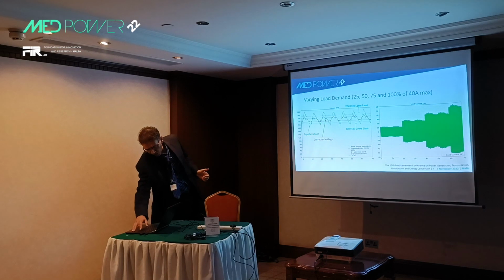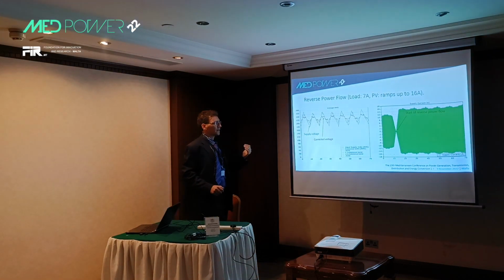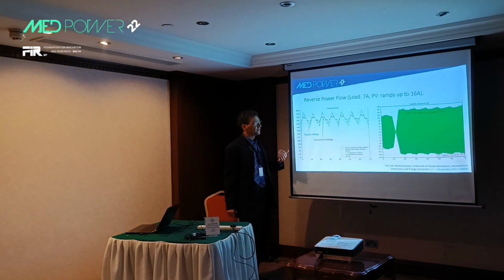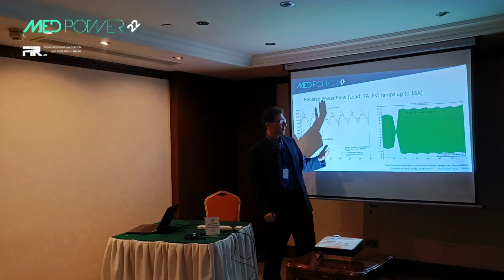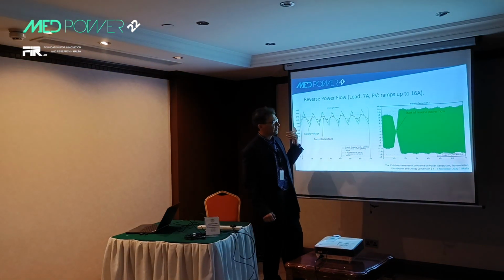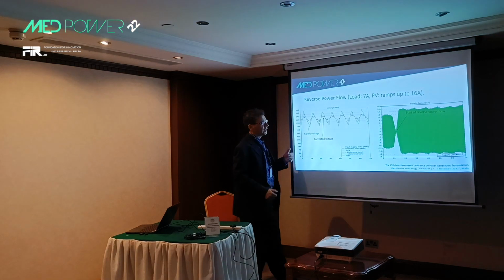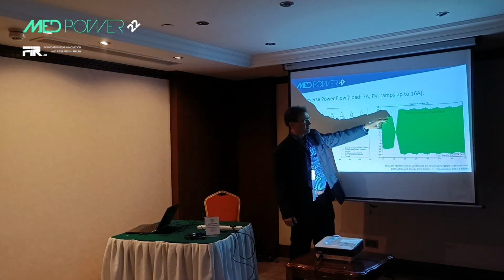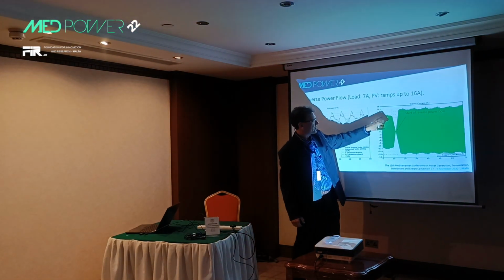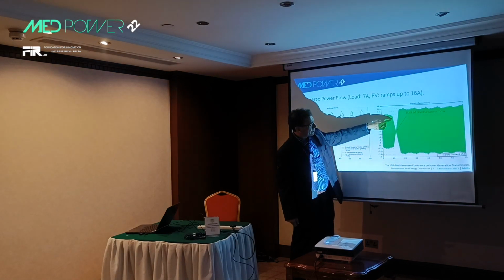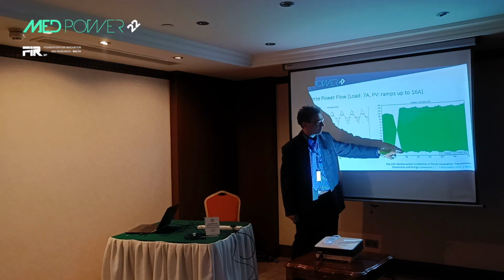Okay? If we come to the other case study that we performed, it is when we're going to have the photovoltaics generating power back into the grid. So we start with a certain load current, I think it was around 7 amps RMS, and we started ramping up the amount of current produced by the PV.